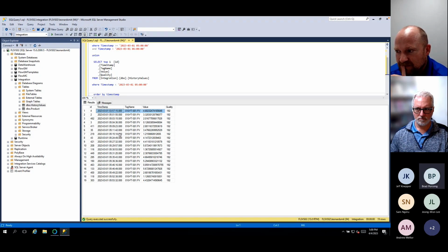Typically qualified values? So you get a numeric value, a quality code, and a timestamp? That's it. Timestamp, quality code, and a value. We call it a TVQ, or a VTQ, or wherever you are in the world, they've got different abbreviations for it. But technically, it's a value, timestamp, and a quality.